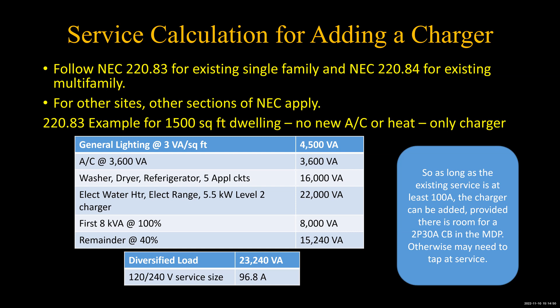The other thing, of course, is you need room for a 2-pole 30 amp circuit breaker in your distribution panel. Otherwise, you may need to do something else, like a line side tap at the service entrance, or maybe even replace the main. Who knows? There are so many options that you discuss with your local electrician. Well, you guys are engineers and architects, so you decide what you want to do yourself, of course. Forget about discussing it with somebody else. You've got the numbers, you've got the calculator.